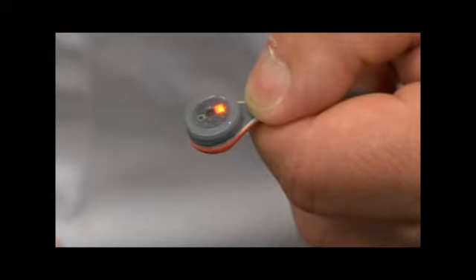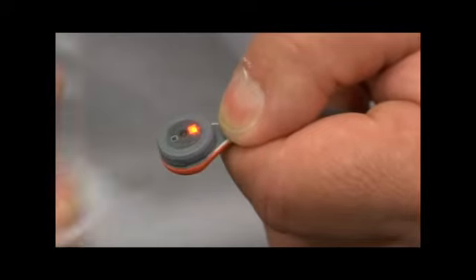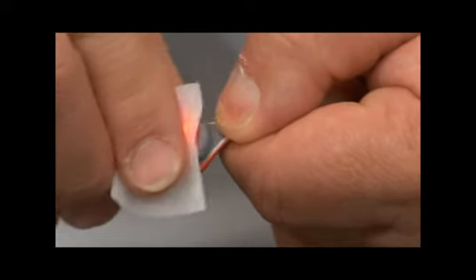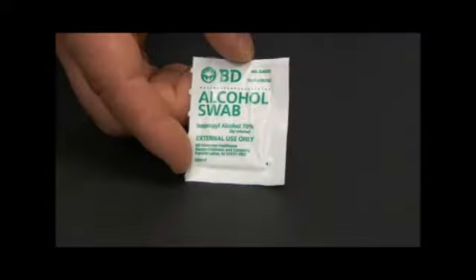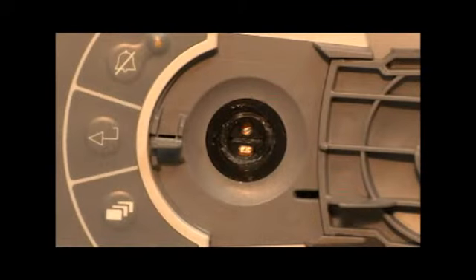After use and before inserting the sensor into the docking station, remove any gel residues or dirt from the sensor and the patient's skin using a 4x4 or alcohol wipe. Before inserting the sensor into the docking station, inspect the condition of the docking station window and gasket. Buildup of gel can cause leaks or occlusions in the calibration window.